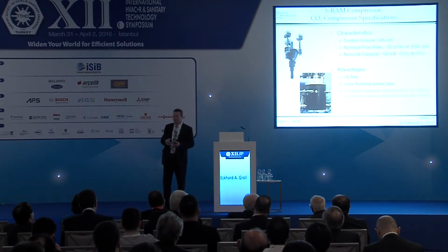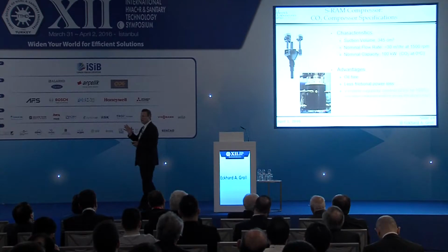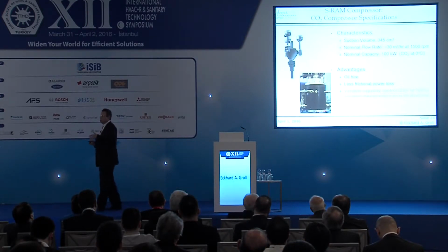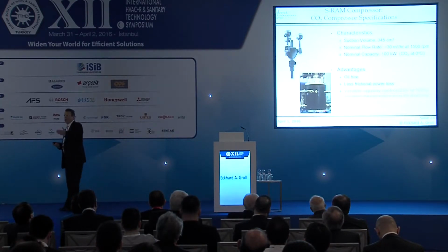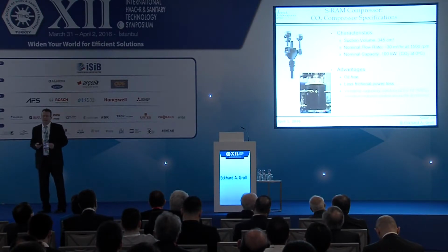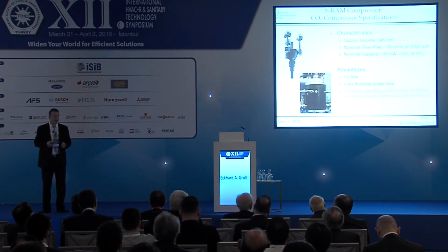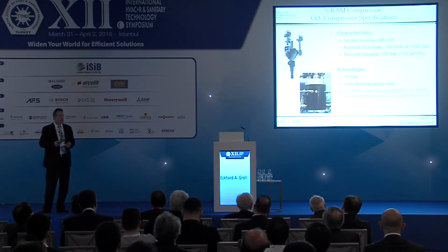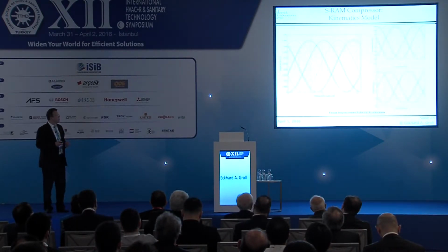I'm moving the bottom dead center, how far I move the piston out. So I have capacity control in the range of 25 to 100% without changing clearance volume, which means almost relatively constant efficiency and very good capacity control. Again, another big advantage of this machine, but maybe a little bit more costly.